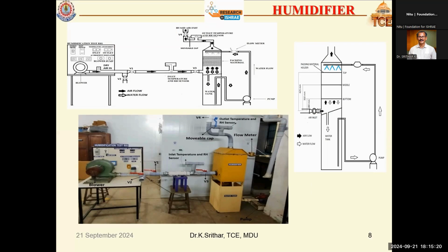You have 3 positions to fix the packing material. What we call packing material, we are using sponge or we can use cellulose pad. Researchers have tried various materials to get more absorption of the water as well as air. The setup principle is very simple. The air coming from the blower goes from bottom to top, whereas the water coming from the top will be sprayed at the bottom.